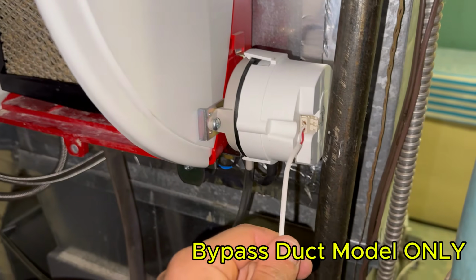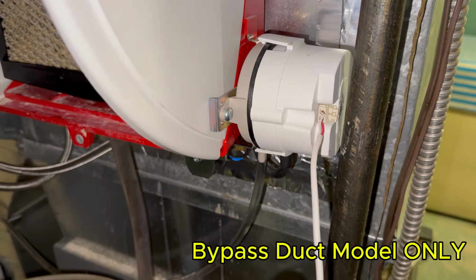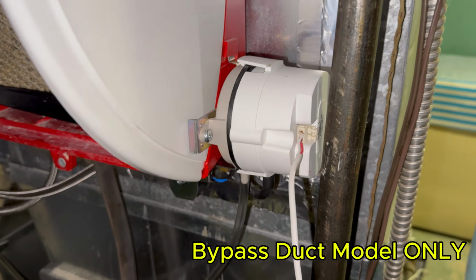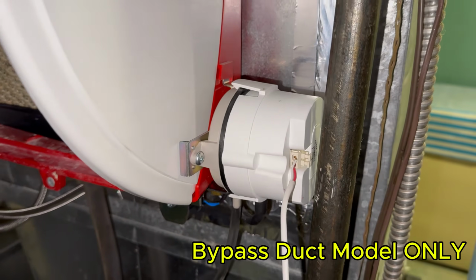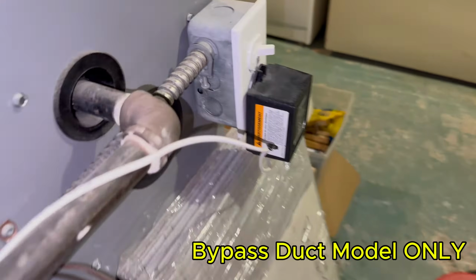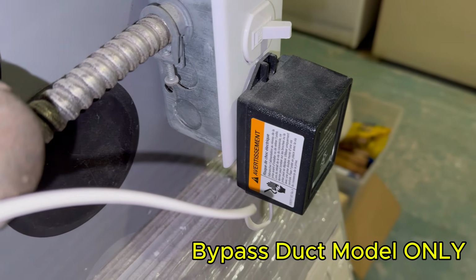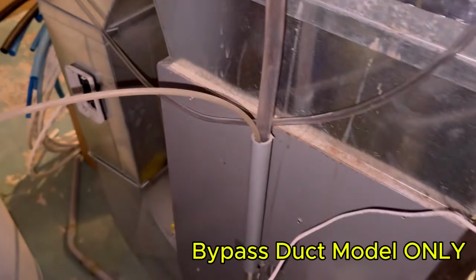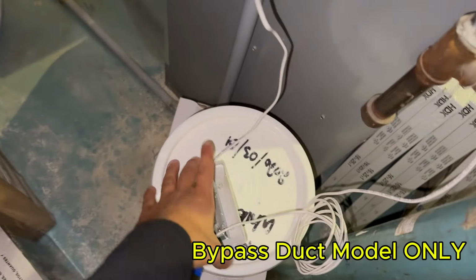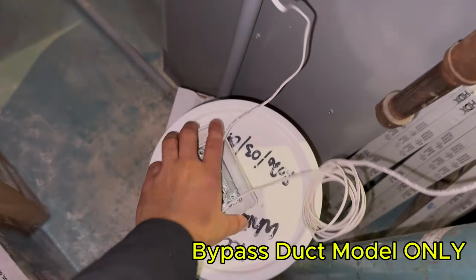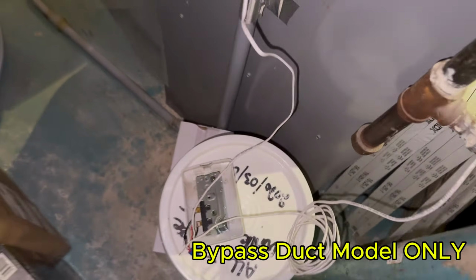Now, when it comes to the wiring of this specific model, what you're going to have is one strand of wire coming from the pressure switch and solenoid. The other end, don't touch it. And one strand of wire coming from the transformer that's included in your package. It's a 24-volt transformer. The other end, don't touch it. And lastly, you're going to have your humidistat, which on the back has 2 black wires.